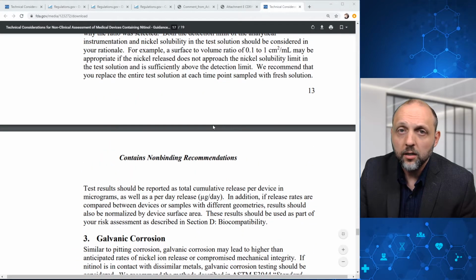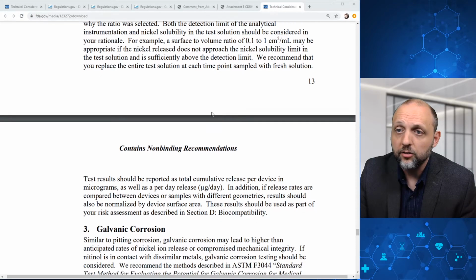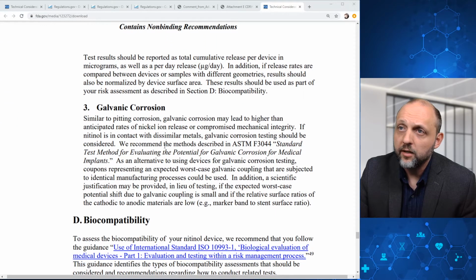If you're going to do this testing, read through and make sure you follow all of these recommendations in this section. And then in terms of galvanic corrosion, similar to pitting corrosion, galvanic corrosion may lead to higher than anticipated rates of nickel ion release or compromised mechanical integrity. If nitinol is in contact with dissimilar metals, galvanic corrosion testing should be considered. FDA recommends the methods described in ASTM F3044. And as an alternative to using devices for galvanic corrosion testing, coupons representing an expected worst-case galvanic coupling that are subjected to identical manufacturing processes could be used.